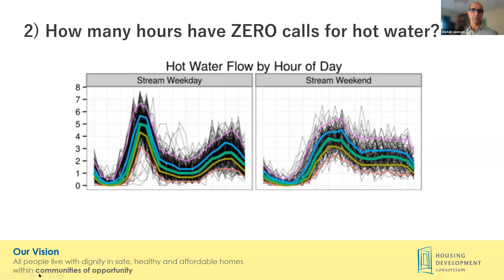And then question 3, how did we do on that one? Just want to step back there for a moment. Most of us were in the 20-second category, a few in the 30-second, only a couple of impatient souls down at 10 seconds. The reality is that according to the American Society of Plumbing Engineers, 1 to 10 seconds is acceptable performance. Between 11 and 30 seconds, we're in the marginal category. If you have to wait more than 30 seconds for hot water, you're likely going to walk away and do something else, letting the hot water run straight down the drain.